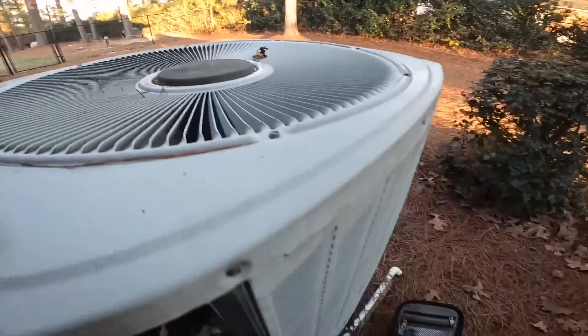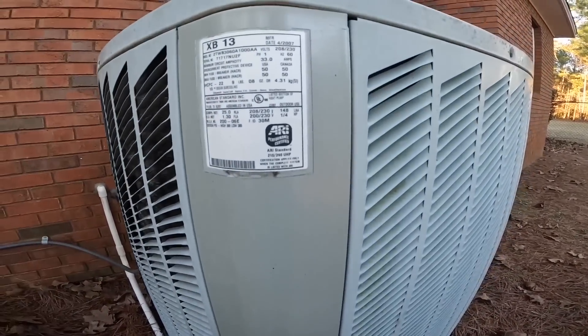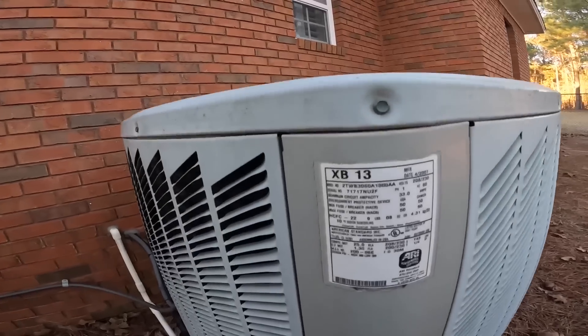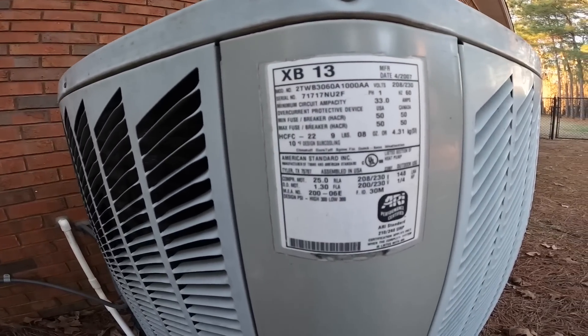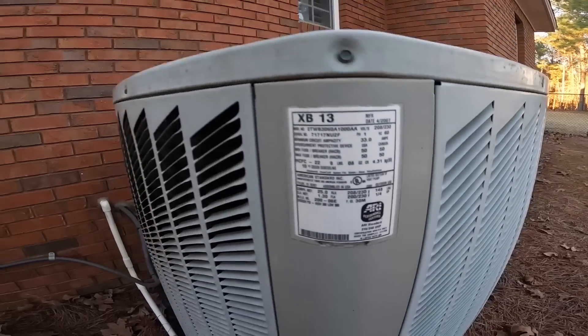Old Climate Master compressor, 2007, R22. Compressor 25 RLA, 148 LRA.